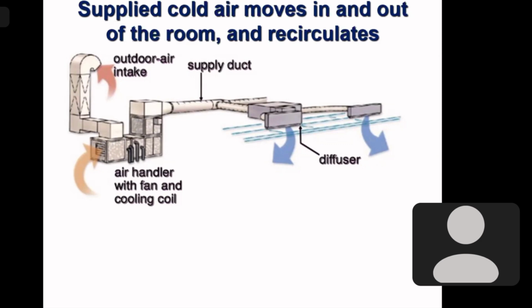So we need some outdoor air continuously. We take some return air, say Q1 quantity, and we add some Q2 quantity of outdoor air with that. So my supply air will now be Q1 plus Q2. We are supplying Q1 plus Q2 quantity of air in the room through the diffuser, but taking back only Q1 quantity. So the Q2 quantity we are not taking back to the air handling unit.